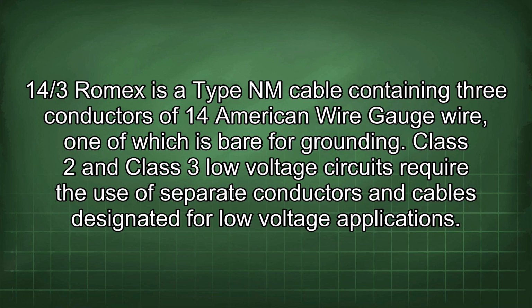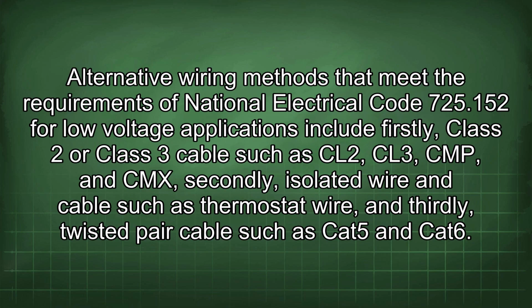is bare for grounding. Class 2 and Class 3 low-voltage circuits require the use of separate conductors and cables designated for low-voltage applications. Alternative wiring methods that meet the requirements of National Electrical Code 725.152 for low-voltage applications include, firstly, Class 2 or Class 3 cables such as CL2, CL3, CMP, and CMX. Secondly, isolated wire and cables such as thermostat wire. And thirdly, twisted pair cables such as Cat5 and Cat6.